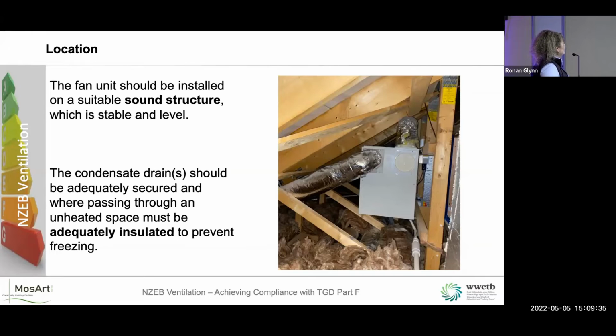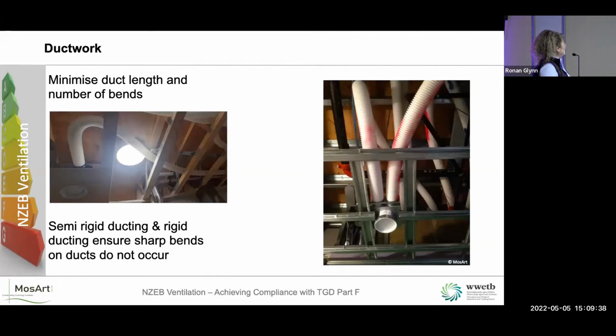Ductwork, there's lots of rules about the ductwork. So you must minimize the duct length and minimize the number of bends. Okay, and that's why semi-rigid and rigid ducting will ensure that sharp bends on ducts do not occur. Okay, so you're talking about nice, slow, sweeping bends. That's why flexible ducting is no longer allowed. So we need rigid or semi-rigid. So minimizing the duct length, all right. By simply turning this plenum towards the unit, we could take off about 900 mil there. So I'd imagine if you got your anemometer out, measured that, turned the diffuser, connected back up the ductwork, you'd get a lot higher flow rate. So then you can turn down your fan a little bit, lowering your EPCs and CPCs in the end. So they're not great examples either. That one's not bad.